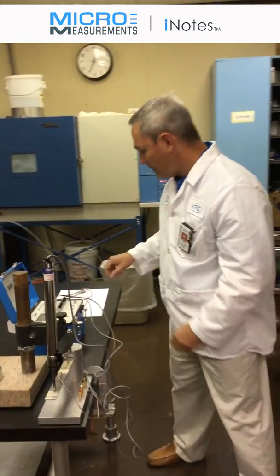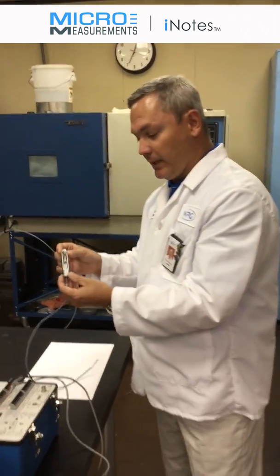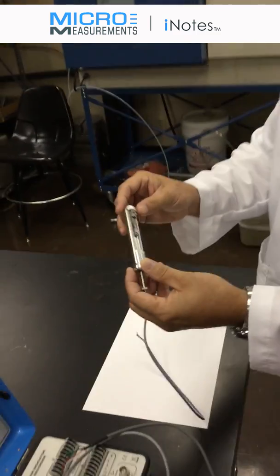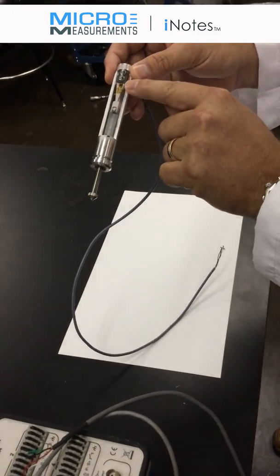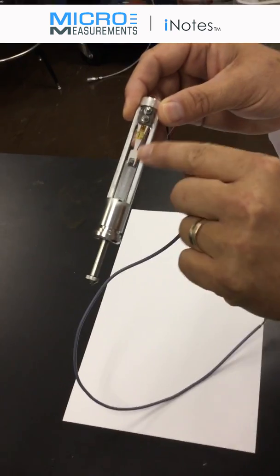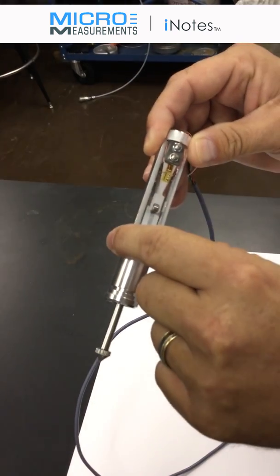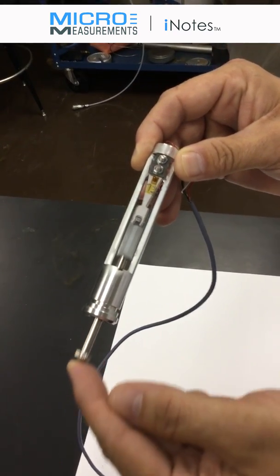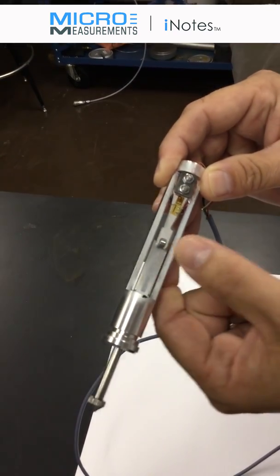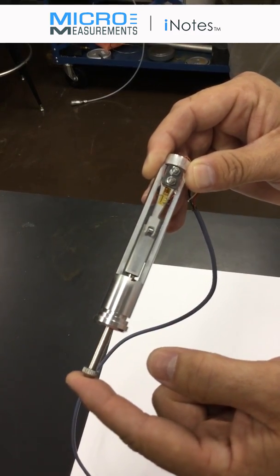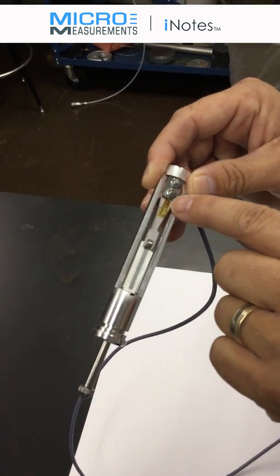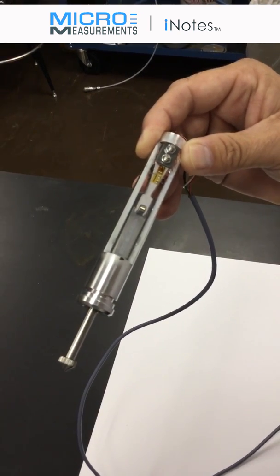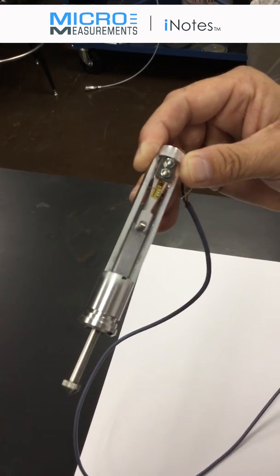Along with this example, I've also got one of our HS10s, and this one has the cover removed. If we take a close look at it, you'll see that you've got two small beams inside of this displacement sensor, along with a wedge. As you push the end of the spindle in, it forces the wedge in between these roller bearings and bends the beams out. If you look closely, you'll see strain gauges installed on these beams, and we're constructing a full Wheatstone bridge, much like any other strain gauge based transducer or load cell.